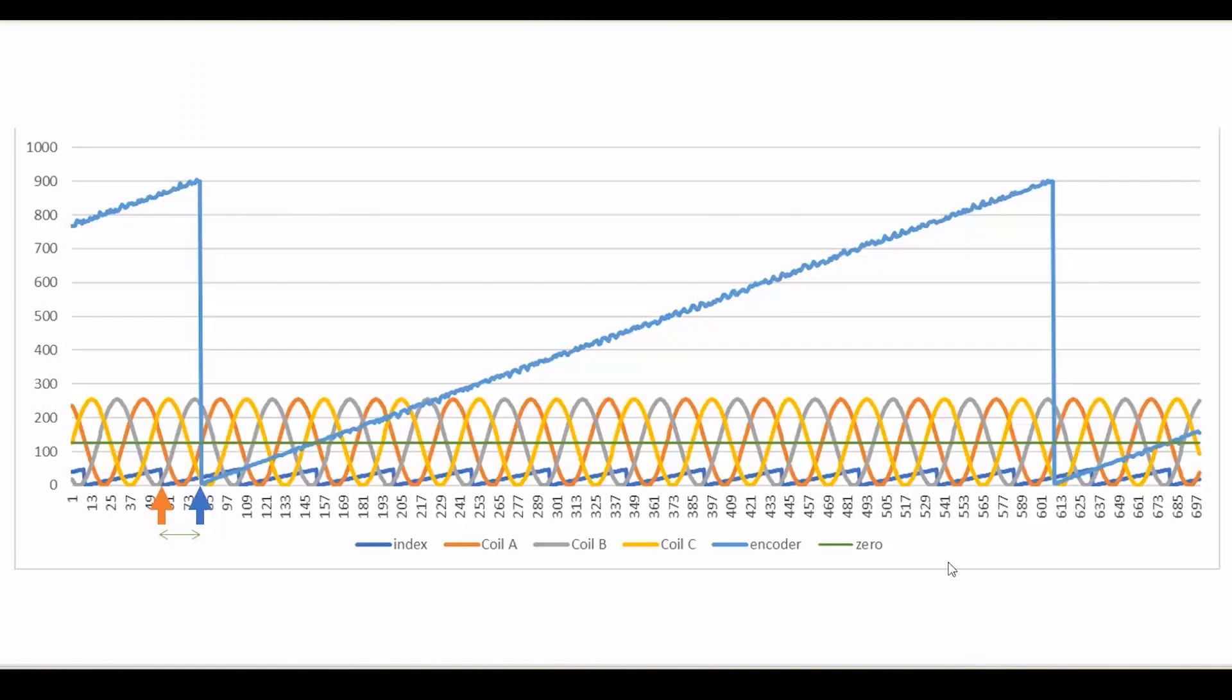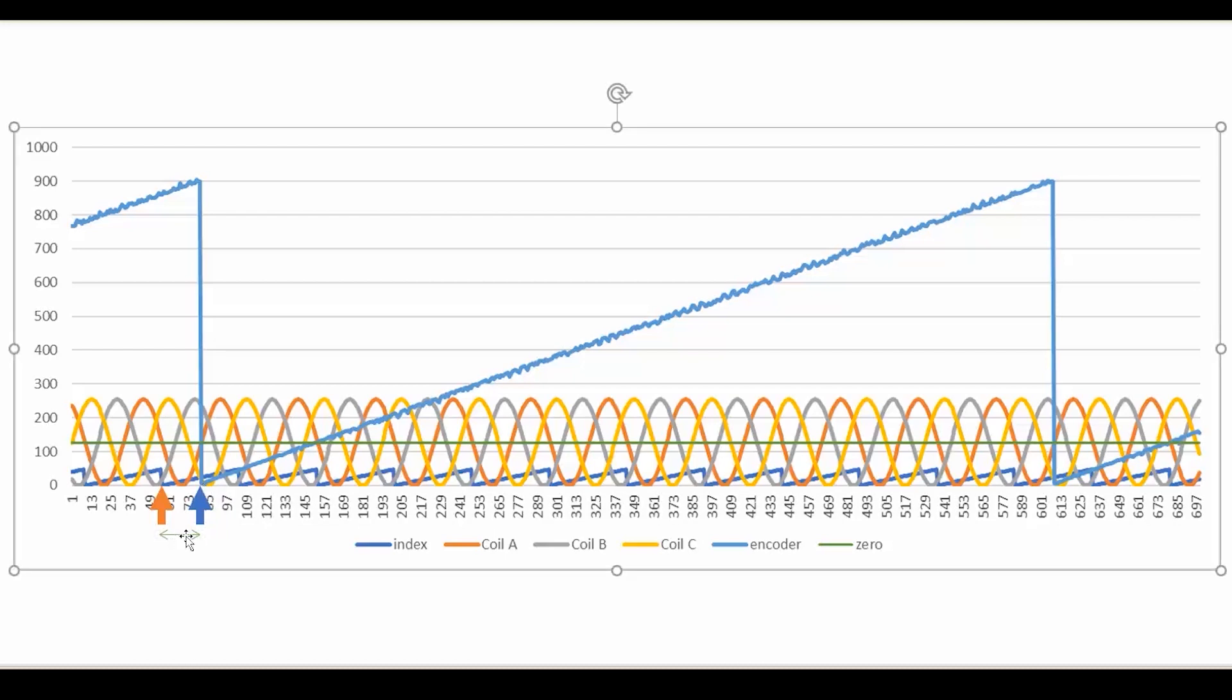If we come back to this chart, you'll see that the beginning of the mechanical revolution does not match the beginning of the electrical revolution. And this is what the synchronization is all about. We need to get these two to start at the same point and therefore they will also end at the same time. And that's what we're going to do by adding this offset on the code.